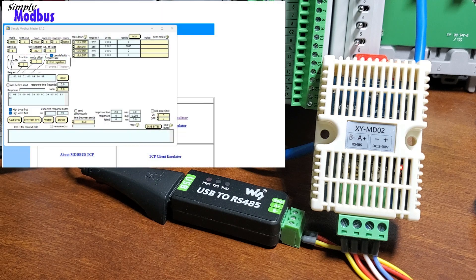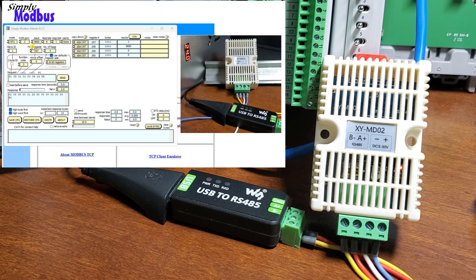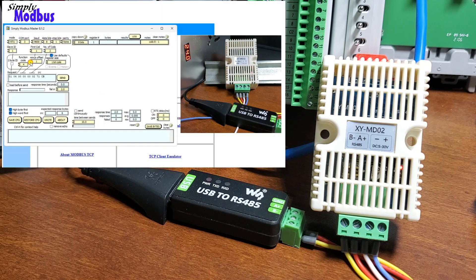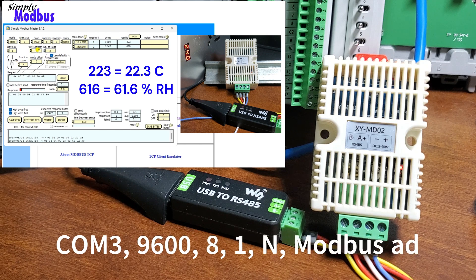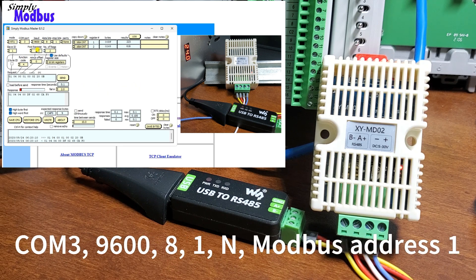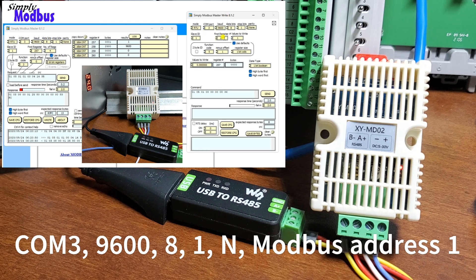Simply Modbus software has extended a 10% discount to ACC Automation readers — use the following URLs to receive a discount on these software packages. Our sensor has Modbus RTU parameters: COM 3, 9600 baud, 8 data bits, 1 stop bit, no parity. The Modbus address on this serial device is 1, which is the default.